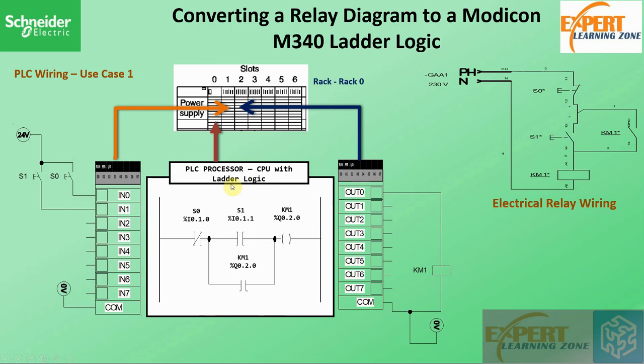This is the ladder logic for this electrical schema. Notice that here we have used two normally open switches in the physical wiring, but in the PLC logic we have represented S0 with a normally closed contact and S1 with a normally open contact. If I press S1, this contact becomes true and closes. Since S0 is a normally closed contact, current will flow through it to S1 and then to KM1, which is the output coil.